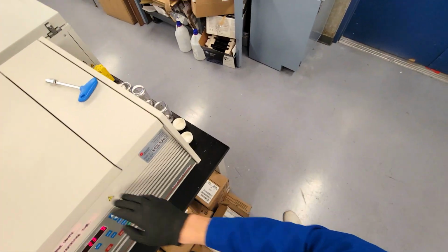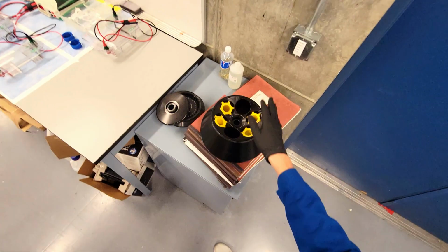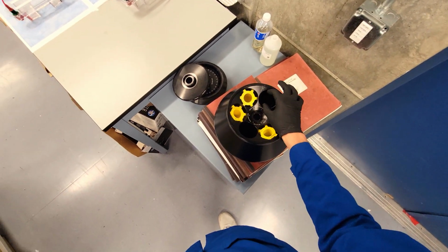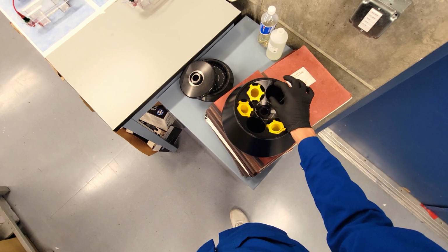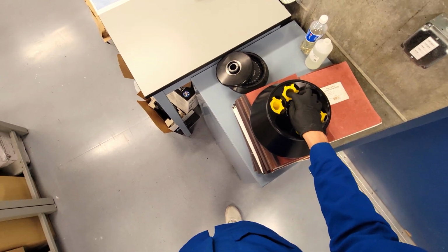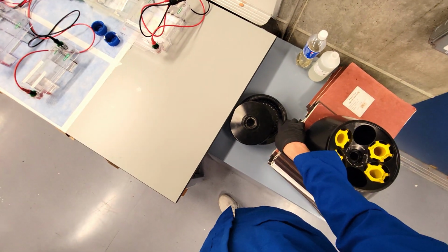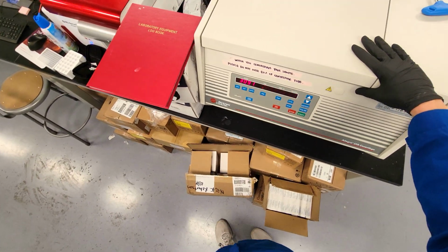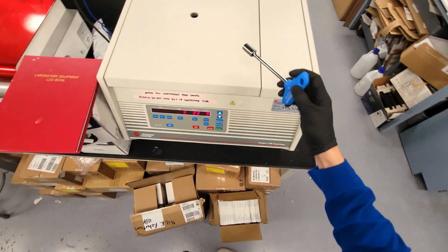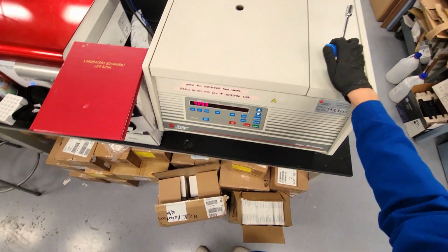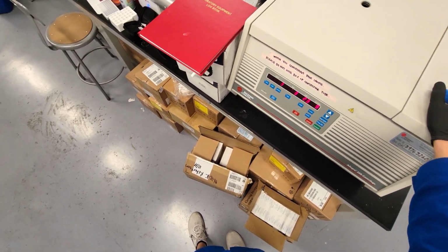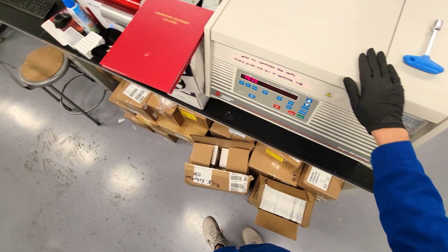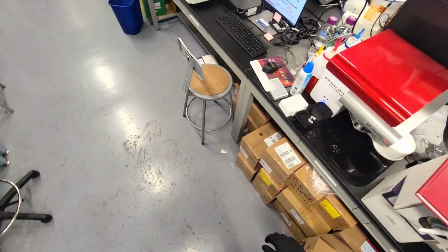So this centrifuge, we can actually change the rotors out on it. So this is a different rotor that holds either 500, I think they're 500 ml bottles, or 50 ml tubes with the inserts. And we have another rotor that holds 1.5 ml tubes in case we need to spin at a colder temperature, because this centrifuge does refrigerate. And you can just take out a bolt in the center with this wrench to change out the rotors if you need to. Well, it's not super balanced, but it's running, so it's fine.